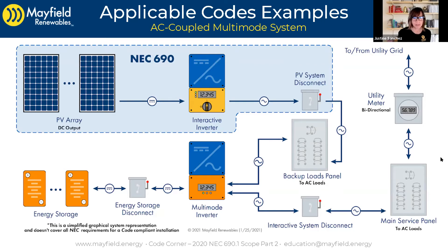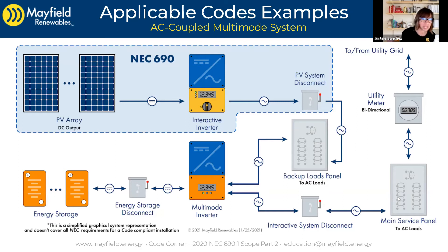An interesting thing to note is we have two inverters here. In the previous slides, there was just a single inverter or multiple microinverters — interactive inverters — not involving anything that could operate in different modes like a multimode inverter. In this case, the multimode inverter means we have moved that PV system disconnect output from being combined or tapping into the main service panel. We've actually moved that connection into what we're calling a backed-up loads panel. That's a key thing to note with this AC coupled system — that connection looks different versus a strict grid-interactive system.